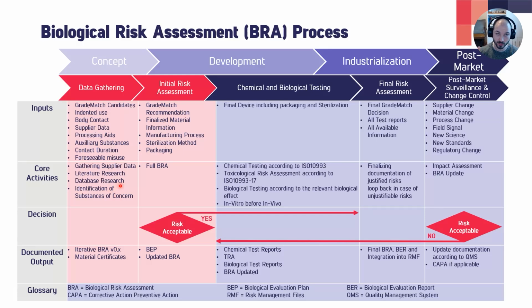Because what we want to do at this phase is we want to identify red flag substances and red flag candidates as early as possible, so we can influence the material recommendation already, so that we don't run into the issue later. Because we take a material and send it to sampling and put it through all this development. We manufacture a tool, we set up industrialization efforts, we buy machines, all of that, which is customized towards one material. And then in the end, in the biological testing, it failed because of a substance of concern we could have spotted in this concept phase. That is what we want to do. We want to fail early. We want to find the substances of concern early in order not to run into the problem later. So we do a little more effort in the concept, in the material selection phase, and do not run into the problem later.